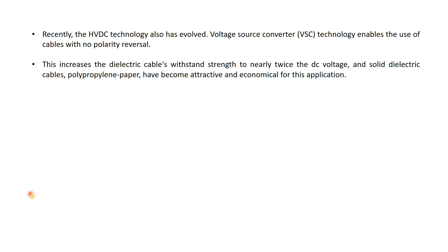So this increases the dielectric cable withstand strength to nearly twice the DC voltage, and solid dielectric cables. This is the technical part, which tells that if high voltage DC is used with the help of VSC technology, then it increases the dielectric cable withstand strength to almost twice.